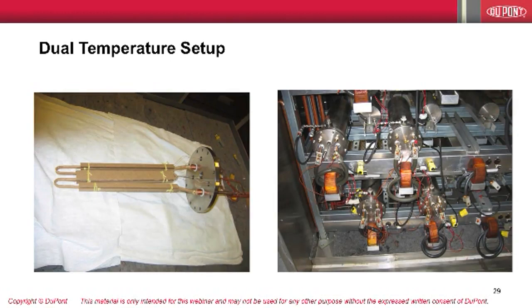Current is then driven through the wire loop by the current transformers shown in the photo on the right, maintaining a constant temperature which is controlled by thermocouples touching the wire insulation. The cylinders are filled with the liquid and the airspace is purged and filled with nitrogen, maintained under positive pressure.